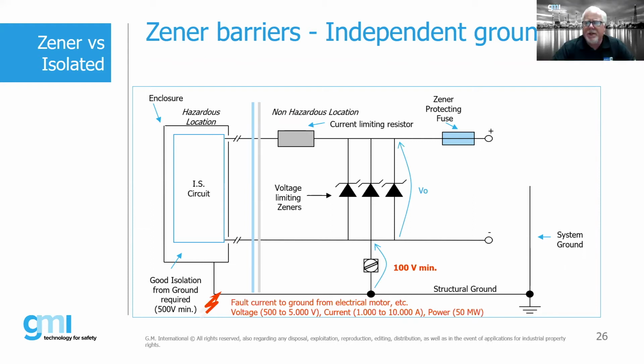So again, this slide shows a little bit of the same of what we already talked about. We have a fault current potentially from a motor or something like that that comes back into the structural earth, that structural ground goes back into our Zener barrier and potentially creates a fault condition at that point. So that's, again, just another way of showing that earthing and grounding of IS Zener barriers is an issue.